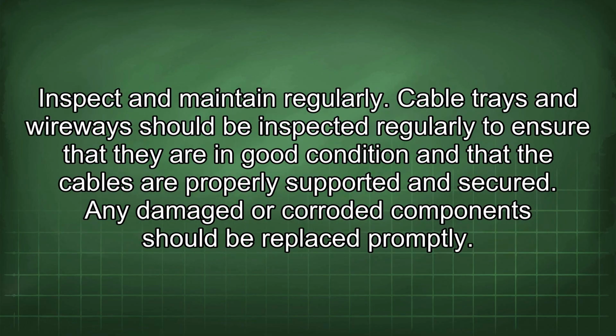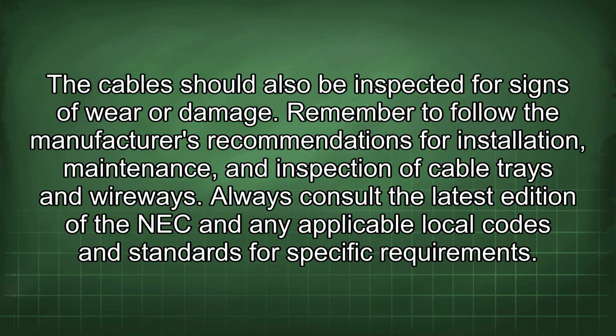Inspect and maintain regularly. Cable trays and wireways should be inspected regularly to ensure that they are in good condition and that the cables are properly supported and secured. Any damaged or corroded component should be replaced promptly. The cable should also be inspected for signs of wear or damage. Remember to follow the manufacturer's recommendations for installation, maintenance, and inspection of cable trays and wireways. Always consult the latest edition of the NEC and any applicable local codes and standards for specific requirements.